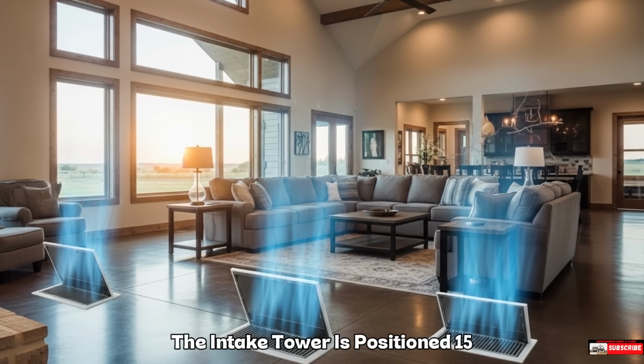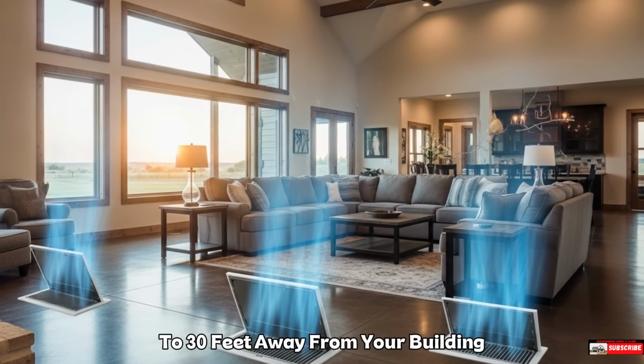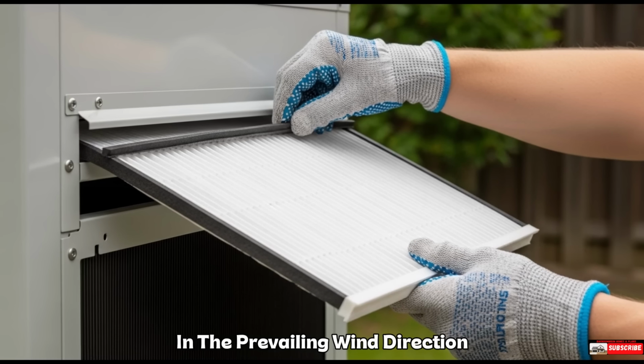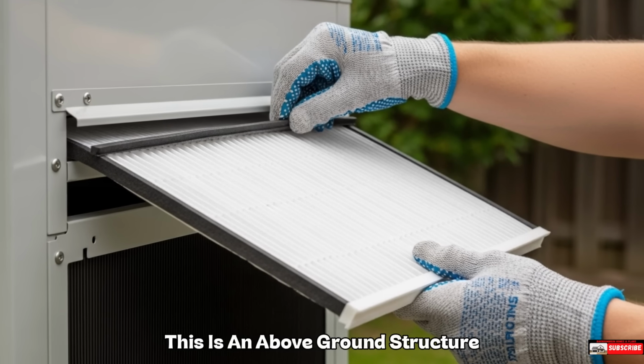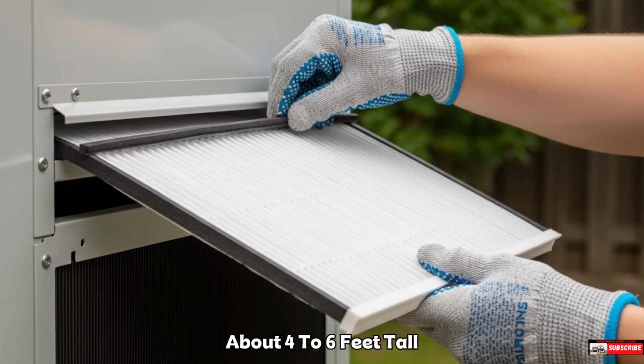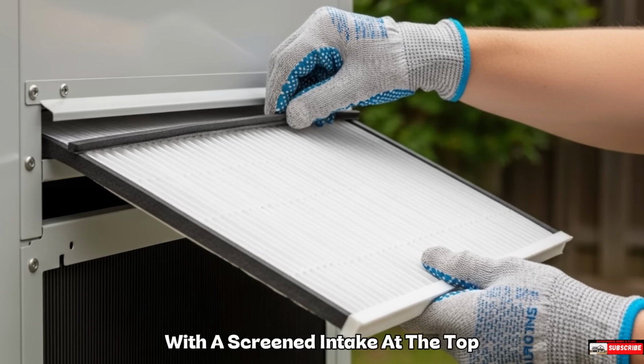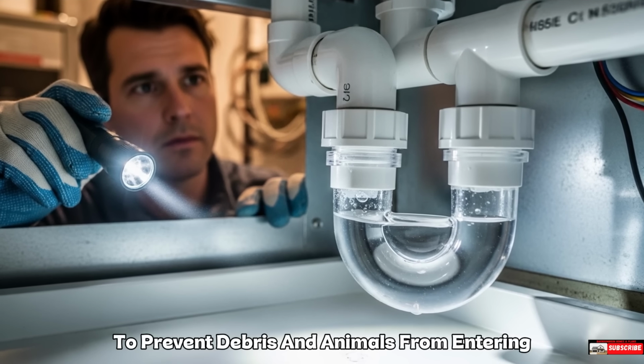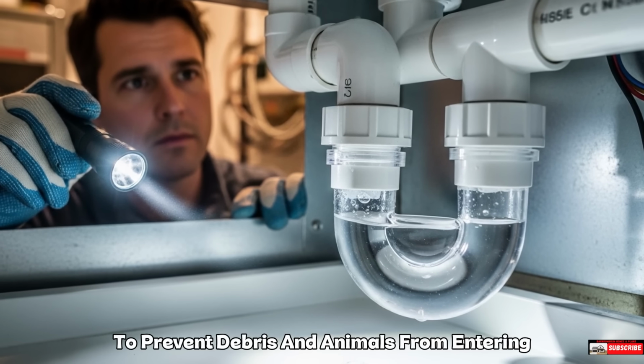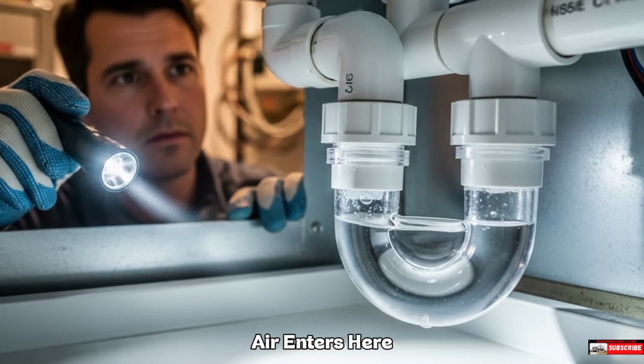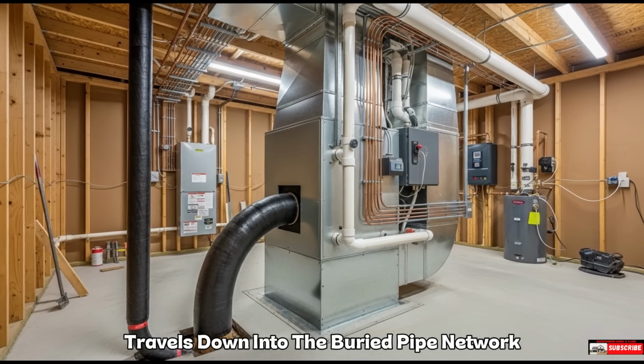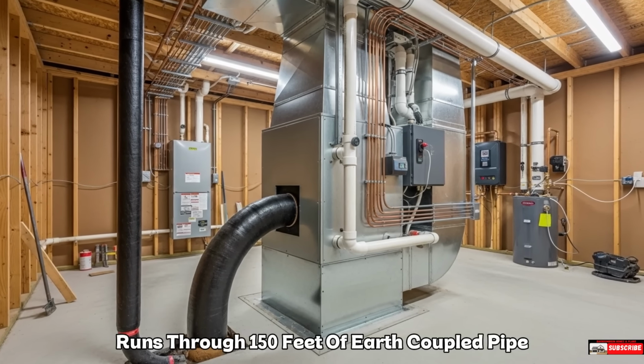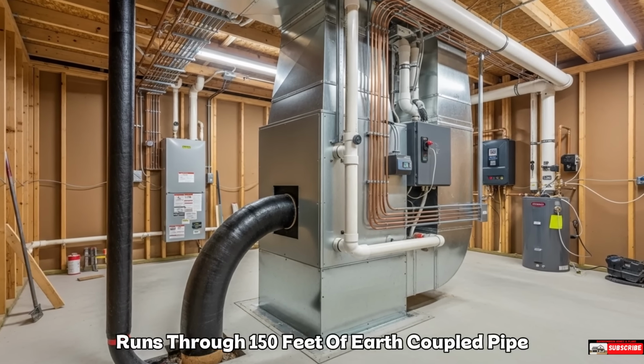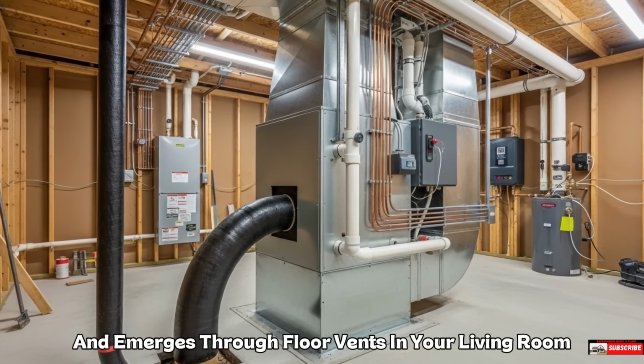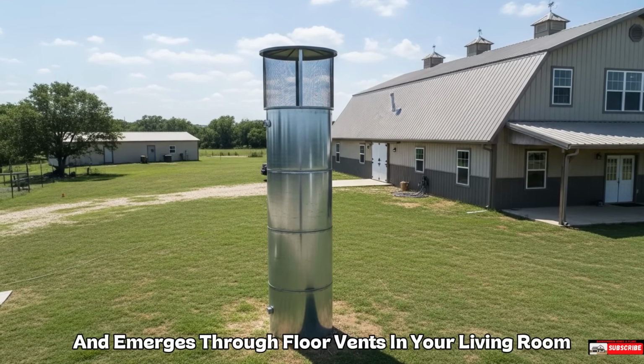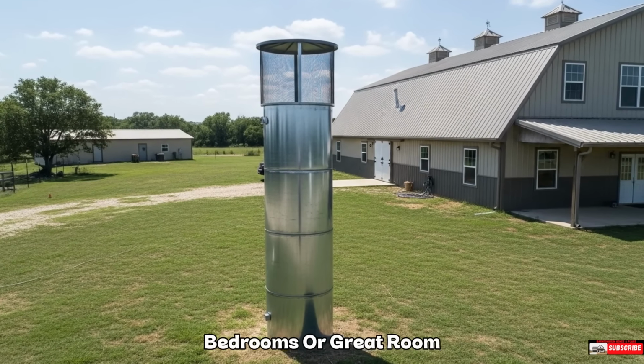The intake tower is positioned 15 to 30 feet away from your building in the prevailing wind direction. This is an above-ground structure about 4 to 6 feet tall, with a screened intake at the top to prevent debris and animals from entering. Air enters here, travels down into the buried pipe network, runs through 150 feet of earth-coupled pipe at 8 feet deep, and emerges through floor vents in your living room, bedrooms, or great room.